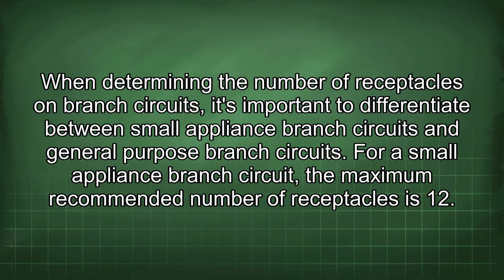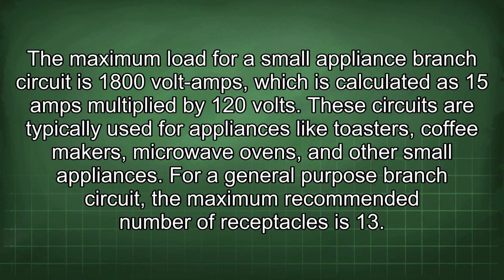When determining the number of receptacles on branch circuits, it's important to differentiate between small appliance branch circuits and general-purpose branch circuits. For a small appliance branch circuit, the maximum recommended number of receptacles is 12. The maximum load for a small appliance branch circuit is 1800 volt amps, which is calculated as 15 amps multiplied by 120 volts. These circuits are typically used for appliances like toasters, coffee makers, microwave ovens, and other small appliances.